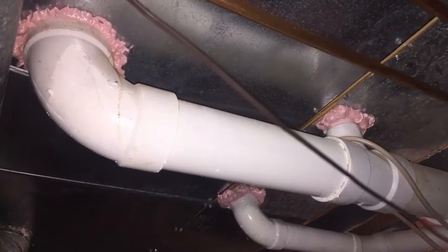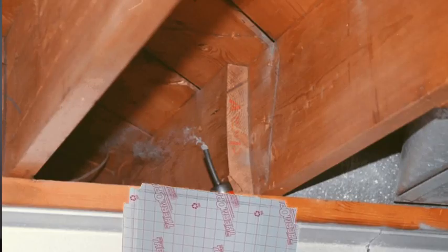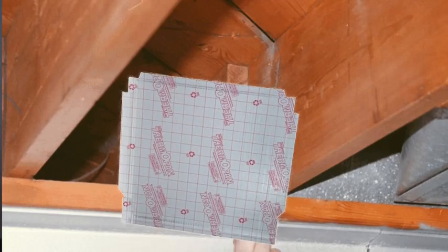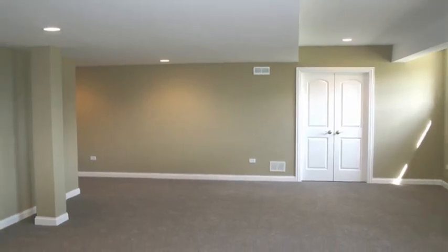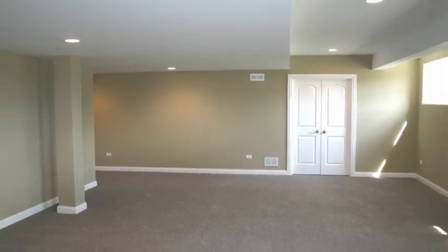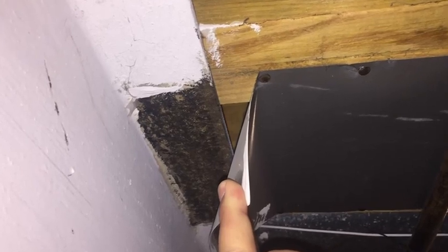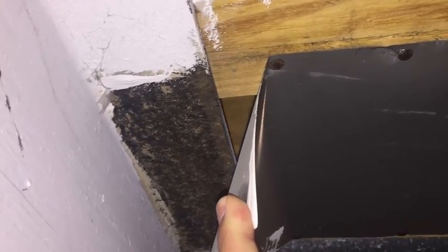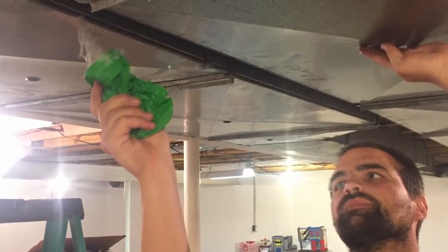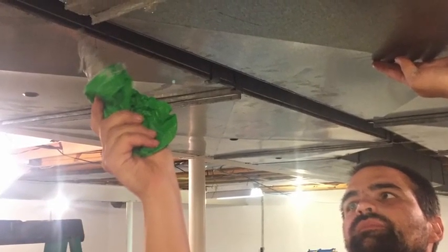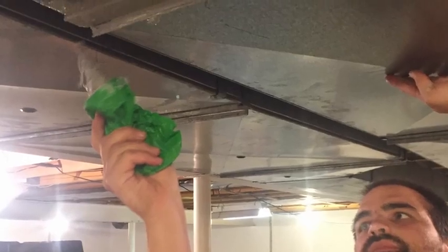Now, if you can get to big leaks like plumbing holes or missing end caps, they're readily fixable during the pre-sealing stage as part of the standard scope of work. But if the basement ceiling has been completely drywalled over, you have a challenge. So these jobs usually require a fair bit of hand pre-sealing before injecting AeroSeal, using a wide range of different products. While the hand sealing normally focuses on the accessible holes that are too big for AeroSeal to seal, most crews also seal some of the smaller gaps in the basement return ductwork to help the AeroSeal machine work faster and create less overspray. The AeroSeal sealant injection time for the return portion of the job is usually double or triple the normal time for the ducted supply side.